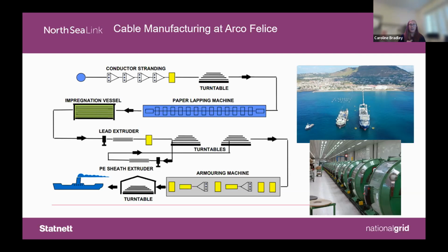For North Sea Link, because we were making so much cable, our main concern was quality control of the manufacturing process - we type tested it and followed all the CIGRE guidance, but with such a large amount of cable we wanted to ensure quality throughout. At each stage we had hold and witness points maintained with the supplier, where we could test the cable, and we also had options to go back and test it later if we felt the quality was slipping. That was key to us being confident such a large quantity of cable could be produced by the factory.